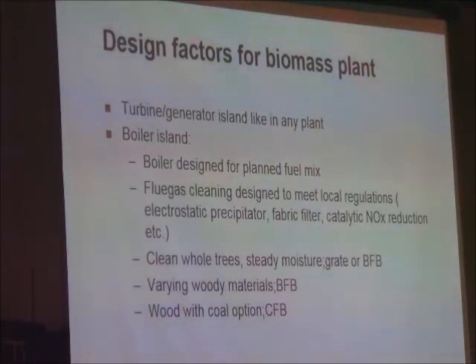For flue gas cleaning, an electrostatic precipitator is often enough, but there are other options. If you want to go even lower, a fabric filter is a bit more efficient at capturing solid particles. NOx is not the main problem when you're not burning green leaves and needles, and if you let the material season in the forest so the needles drop, very little nitrogen reaches the plant. But there's also catalytic reduction if required by authorities.